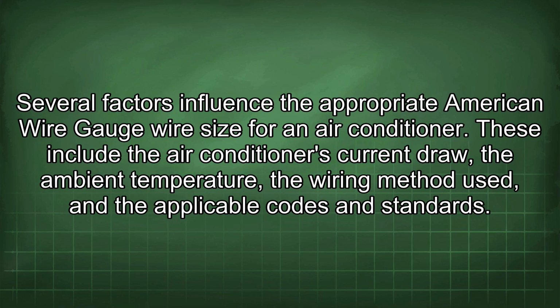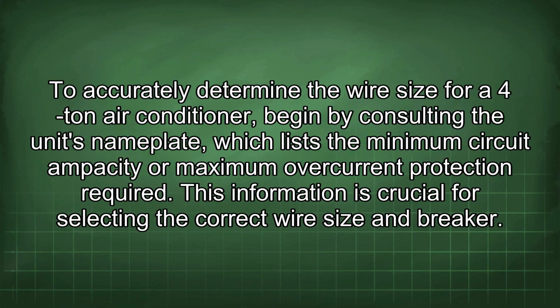Several factors influence the appropriate American wire gauge wire size for an air conditioner. These include the air conditioner's current draw, the ambient temperature, the wiring method used, and the applicable codes and standards. To accurately determine the wire size for a 4-ton air conditioner, begin by consulting the unit's nameplate, which lists the minimum circuit ampacity or maximum overcurrent protection required. This information is crucial for selecting the correct wire size and breaker.